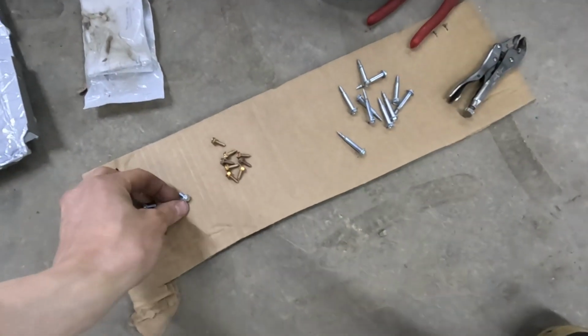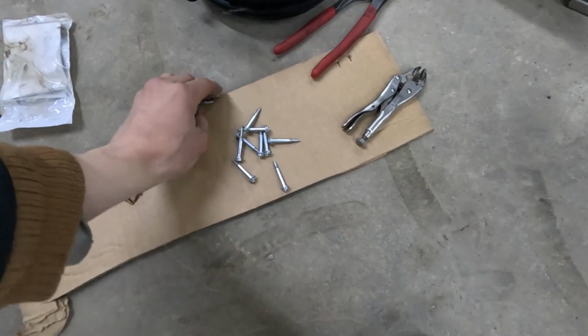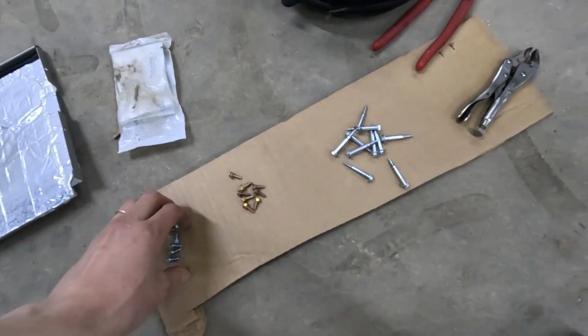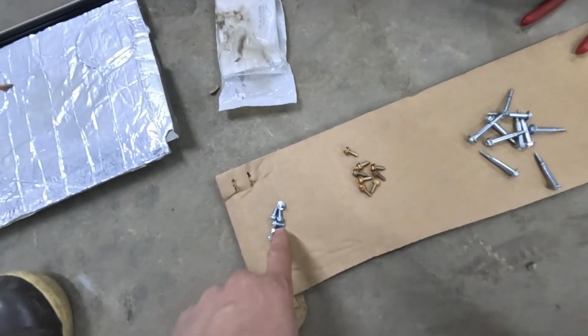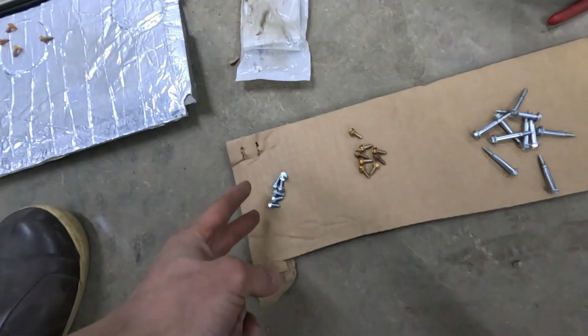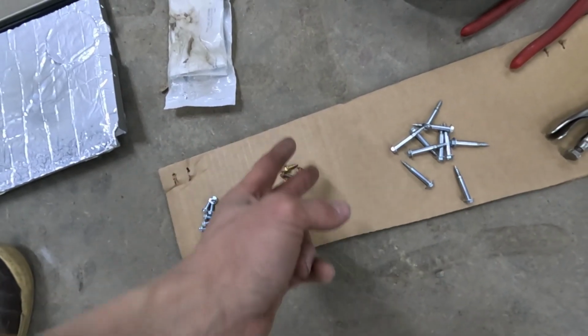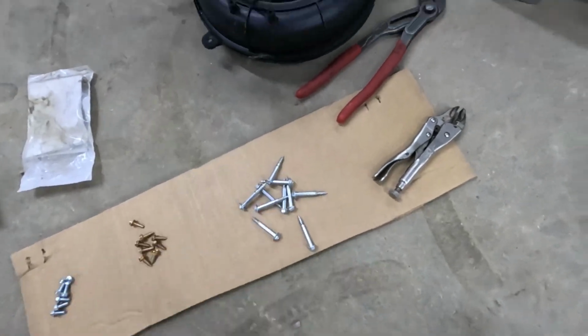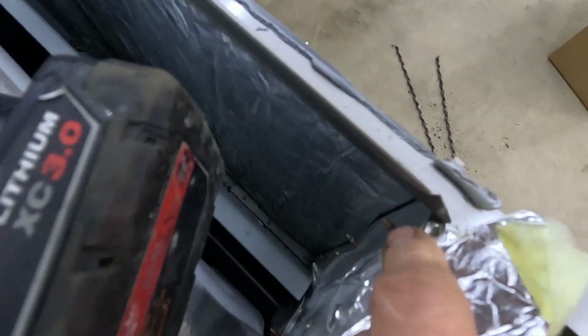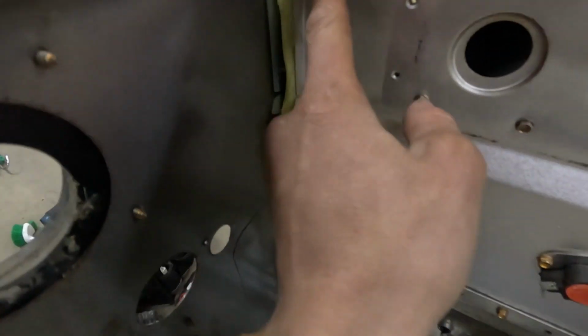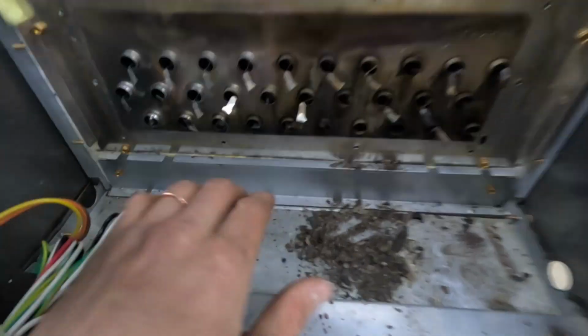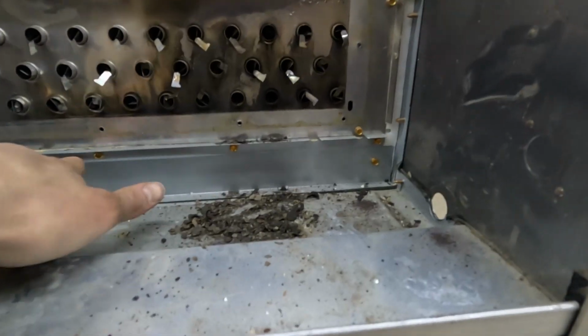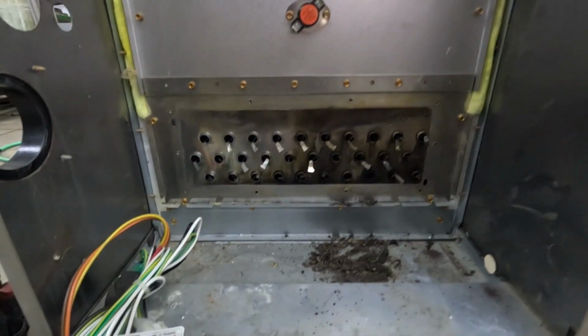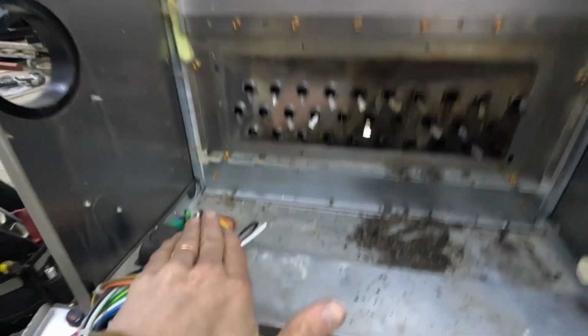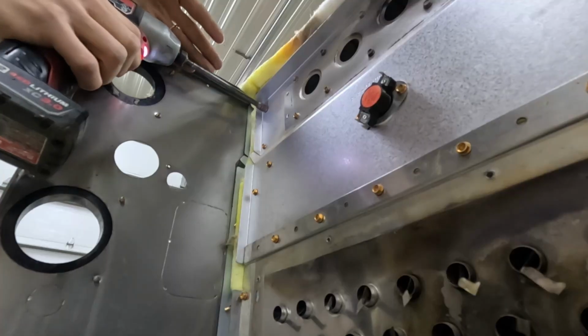And then I like to put the screws all just on a piece of cardboard in their separate pile. If they're special screws, special lengths or something, sometimes I'll mark what they are. But I just know these fine thread ones are for the condensate trap and the combustion blower. These ones are for the pressure switch and the burner box, and these ones are for the collector box. If you look down on the inside of the furnace, you can see there's a support rib going all the way down on both sides. So it's just this row of screws that has to be removed. There's like a separate bracket right here, and we have to remove this entire bracket in order to get this out. And thankfully, I think that gives us enough clearance that we don't have to remove the entire wiring harness.